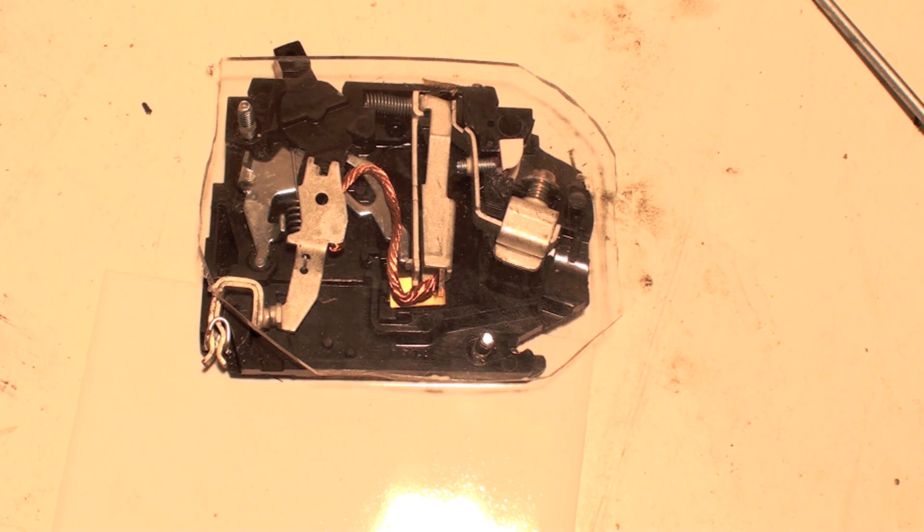If it's running normally, here again right through the wire, through here and back to there and out. Now there is a bi-metal in these. A bi-metal is just two different metals put together, usually copper and steel. They expand and contract at different rates so that if they heat up or cool down, they'll actually bend because copper expands a lot faster or a lot more than steel does.